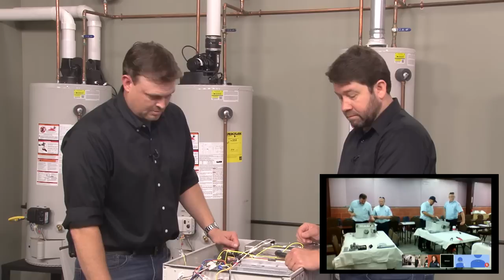You should be able to, and we can even pull the burner out in a moment. You can look at the burner and we can talk about how you clean that out. You can put it in a degreaser or use water, but then you need to get it dried off, with some compressed air, and get a vacuum in there to vacuum it all out.